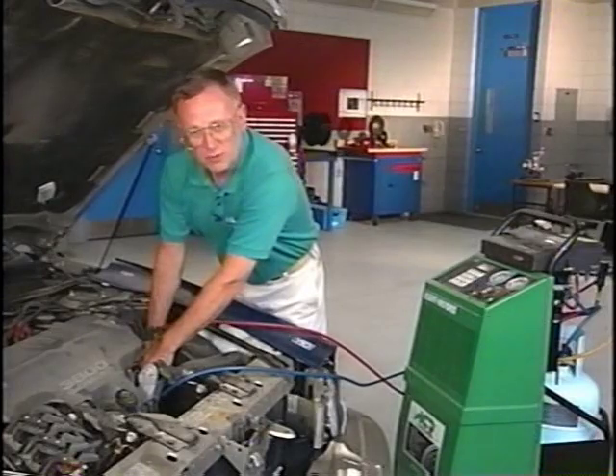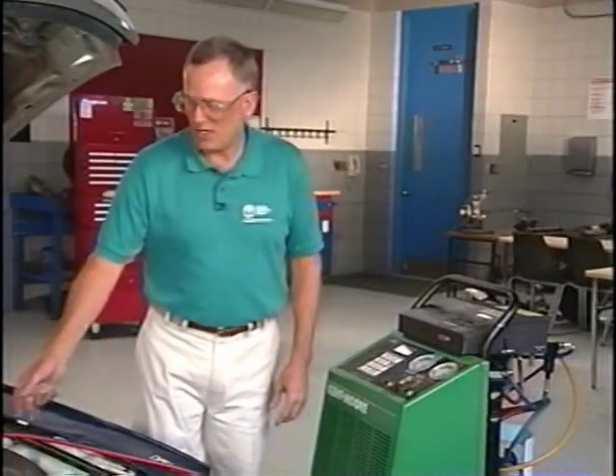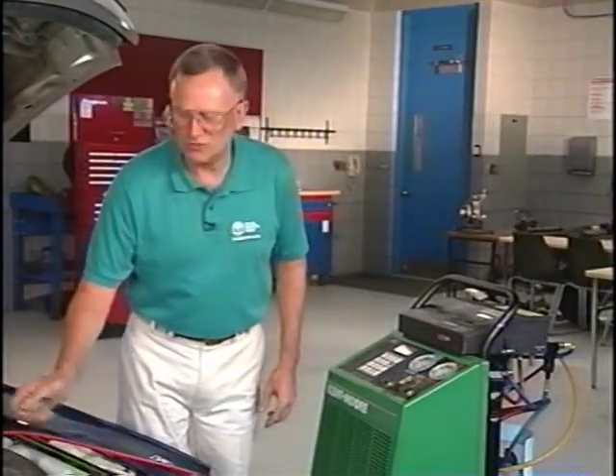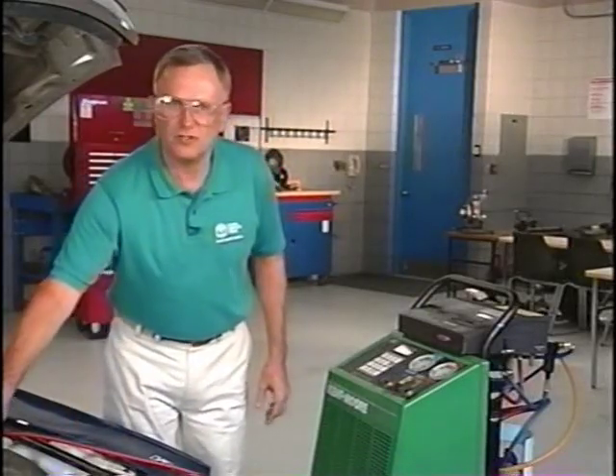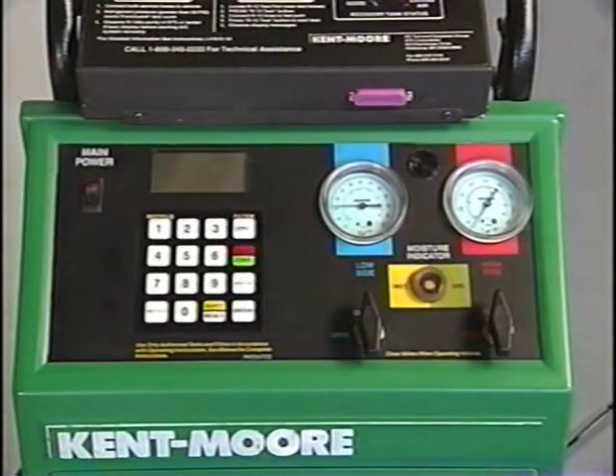Now I want to open that coupler. Now that we've connected the high side hose and the low side hose and we've opened both the couplers to the system, I want to go to the ACR4 control panel here, and I want to look at the high side gauge and the low side gauge to determine the amount of refrigerant in there.